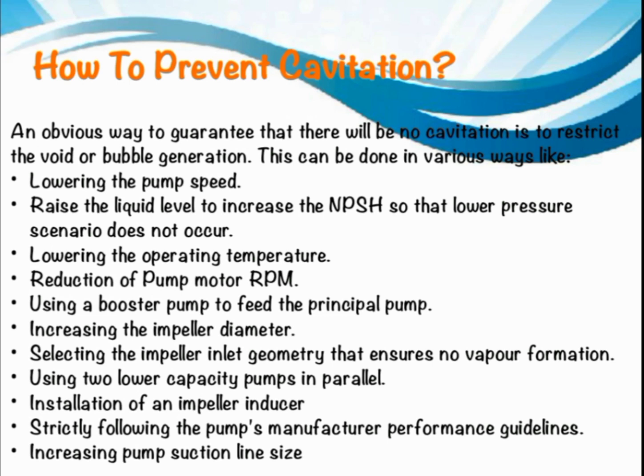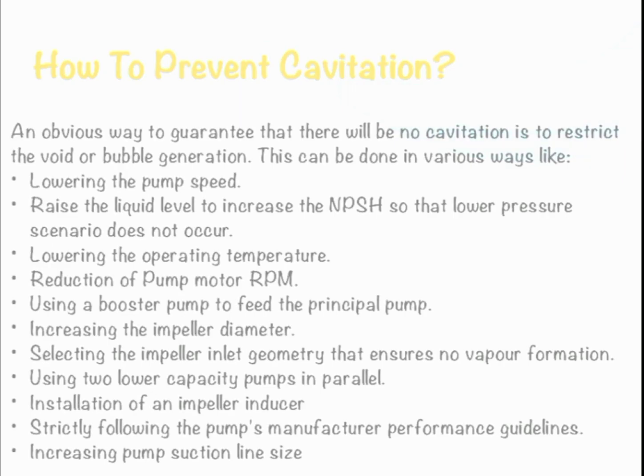so that a lower pressure scenario does not occur, lowering the operating temperature, reduction of pump motor RPM, using a booster pump to feed the principal pump, increasing the impeller diameter, selecting an impeller inlet geometry that ensures no vapor formation, using two lower capacity pumps in parallel, installation of an impeller inducer.